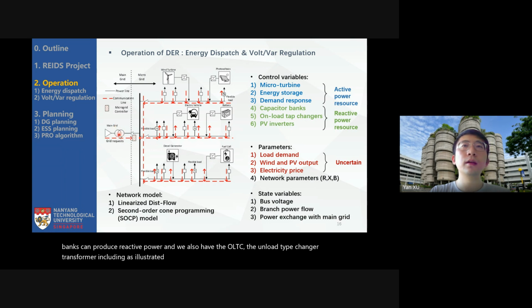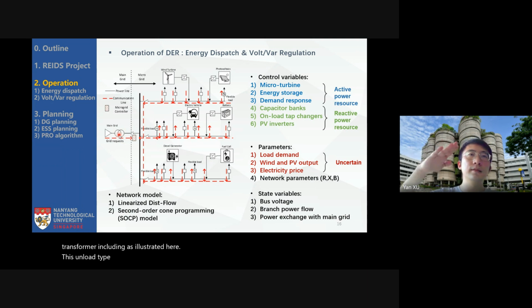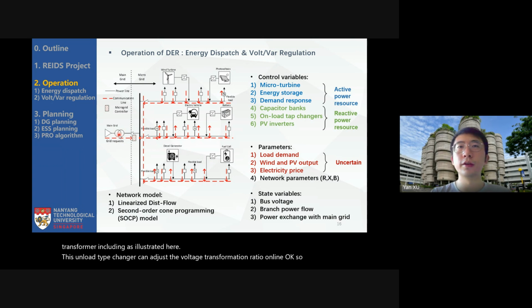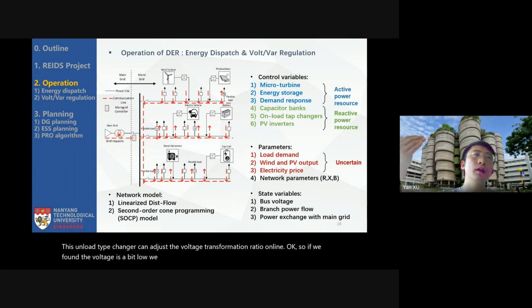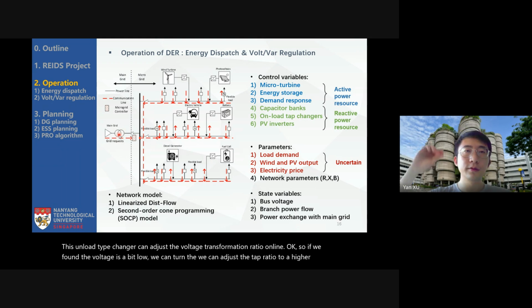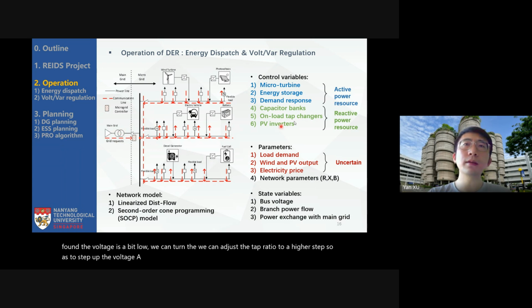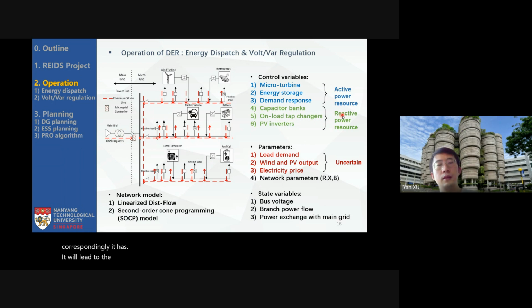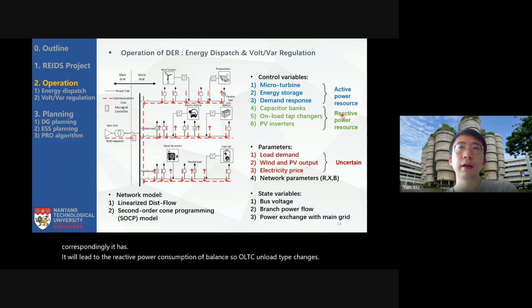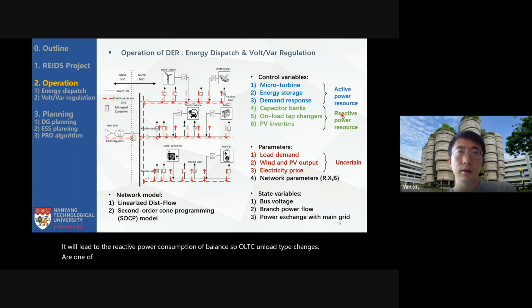This on-load tap changer can adjust the voltage transformation ratio online. So if we found the voltage is a bit low, we can adjust the tap ratio to a higher step, to step up the voltage. By doing that, we also regulate the voltage, and correspondingly it leads to reactive power consumption or balance. So OLTC, on-load tap changers, are one of the reactive power sources.